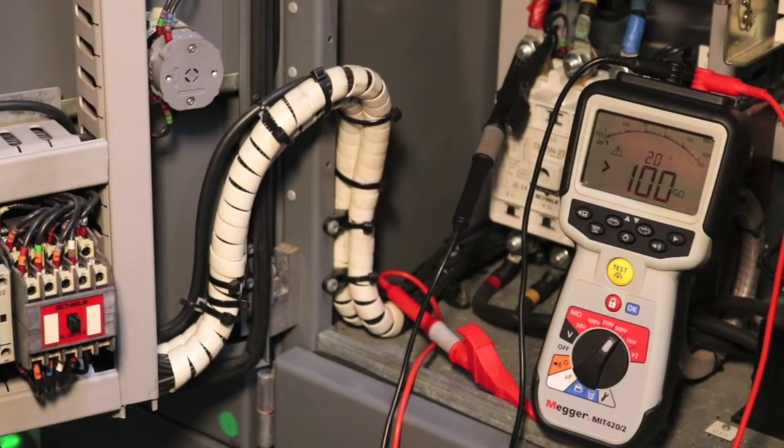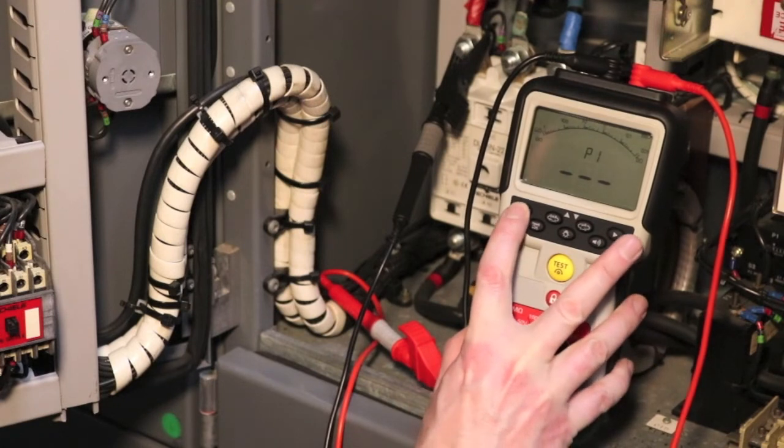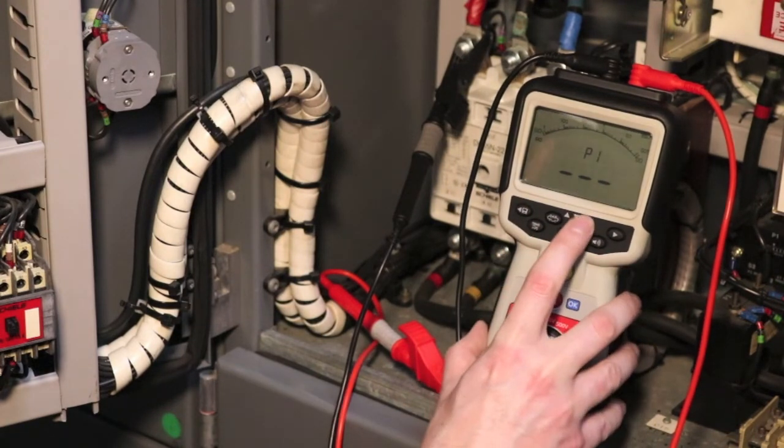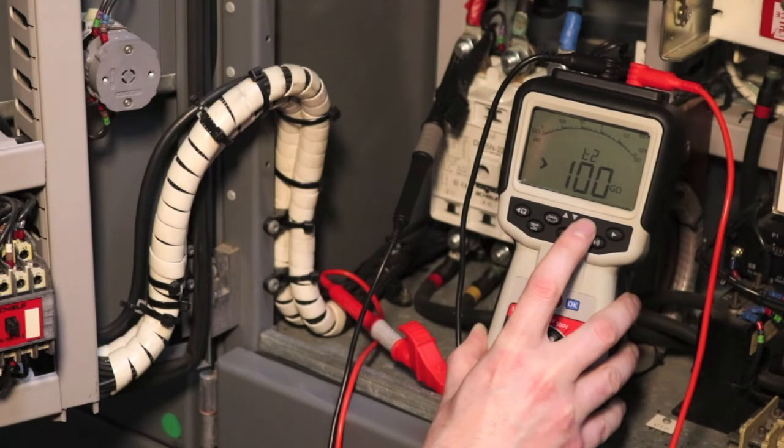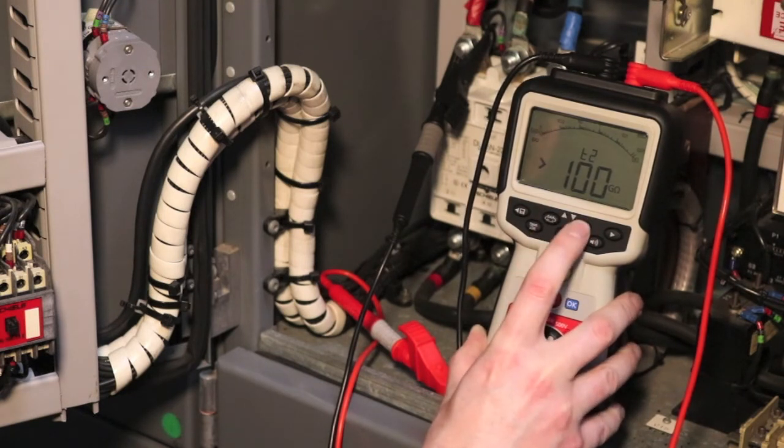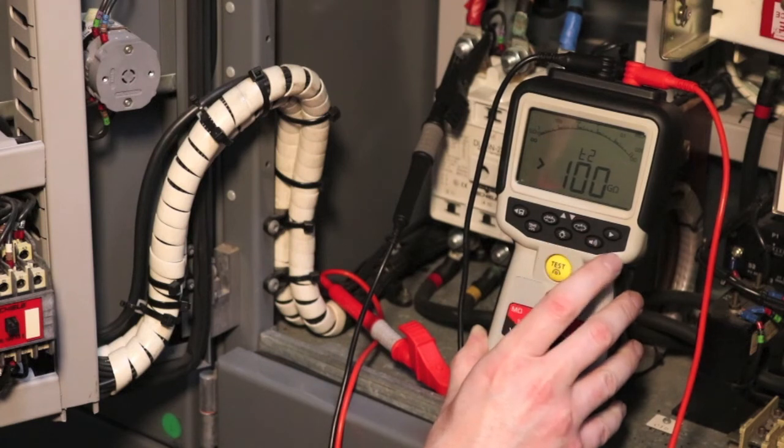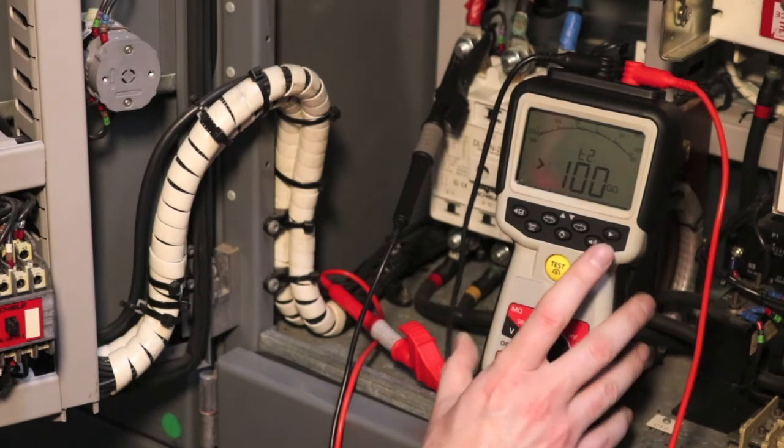So coming up towards the end of the test now you can see the meter has actually reached the maximum reading of 100 gig ohms for the 500 volt range. At the end of the test there's no actual PI ratio value being recorded. You can scroll through readings to get the one minute values and the 10 minute values but presumably because it's gone over that 100 gig ohm max reading for the range there is no PI ratio recorded.